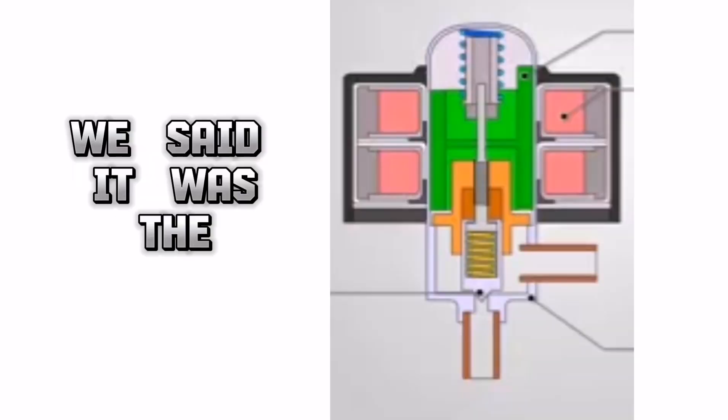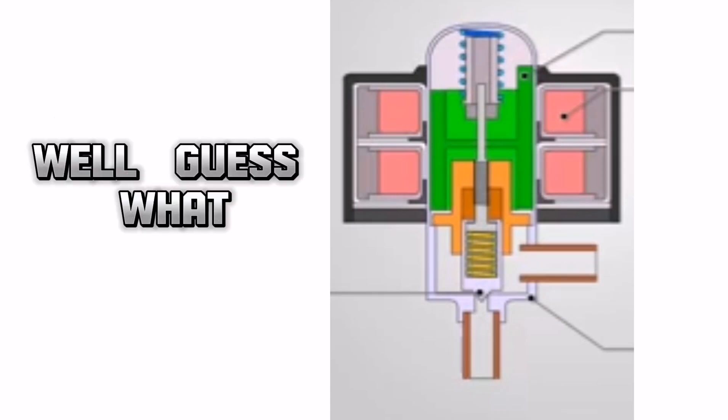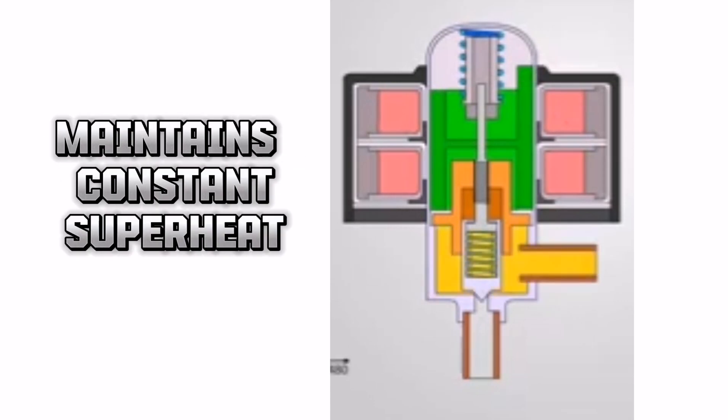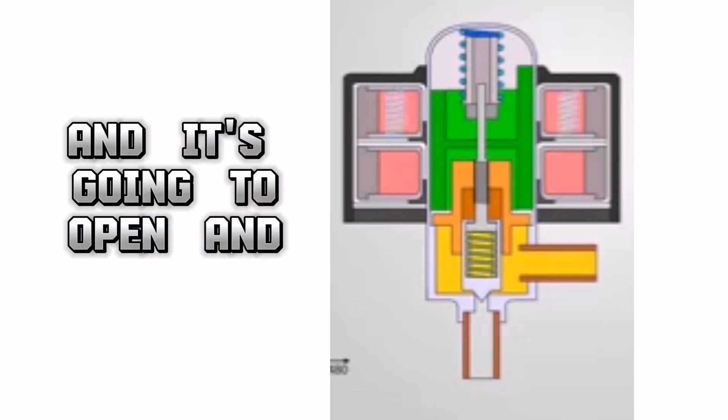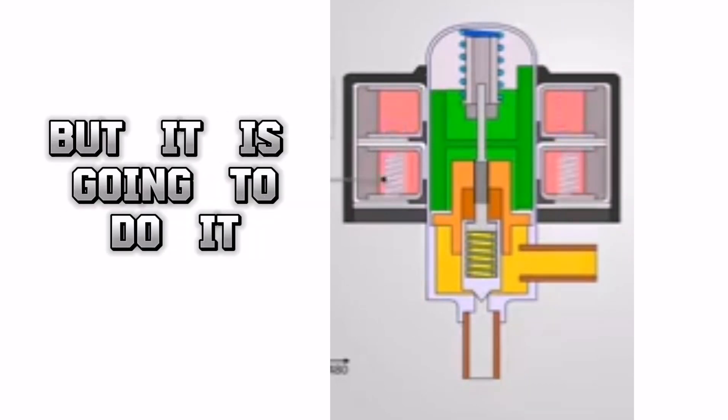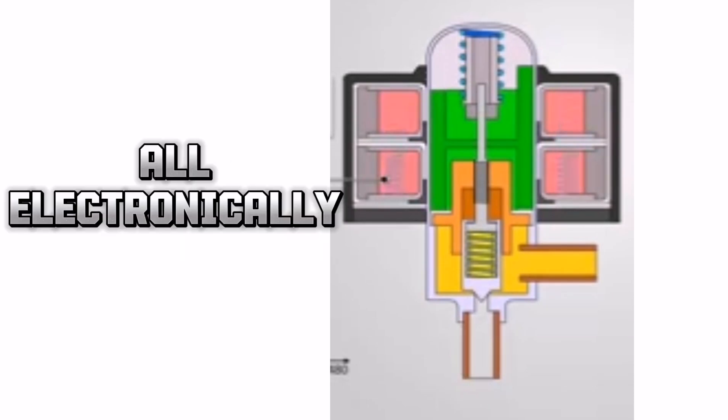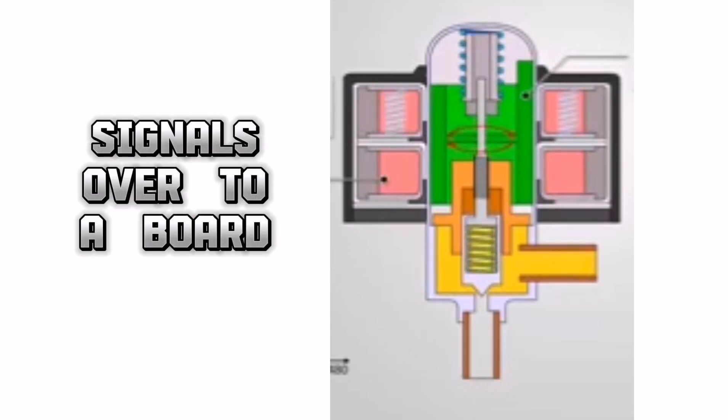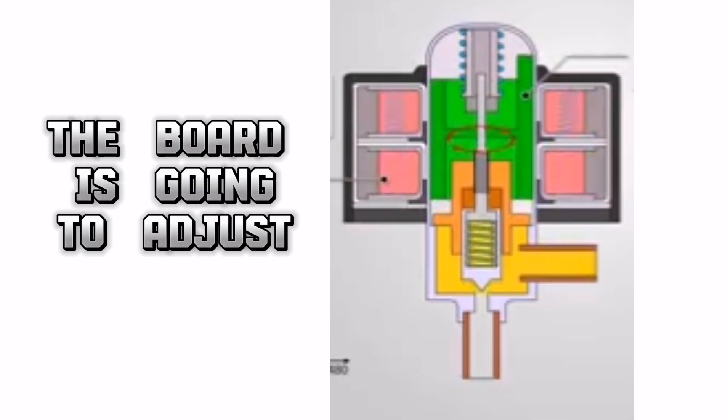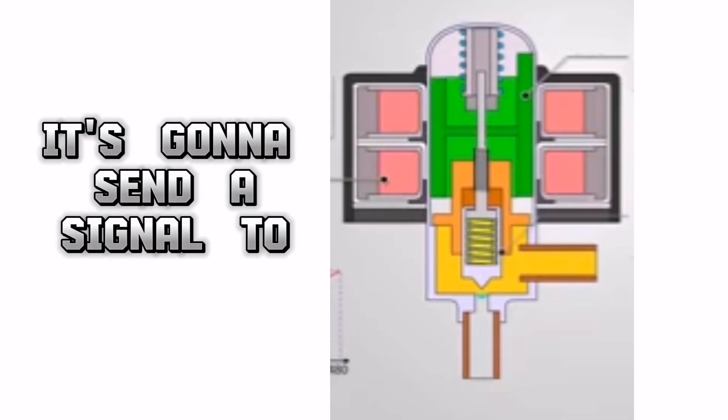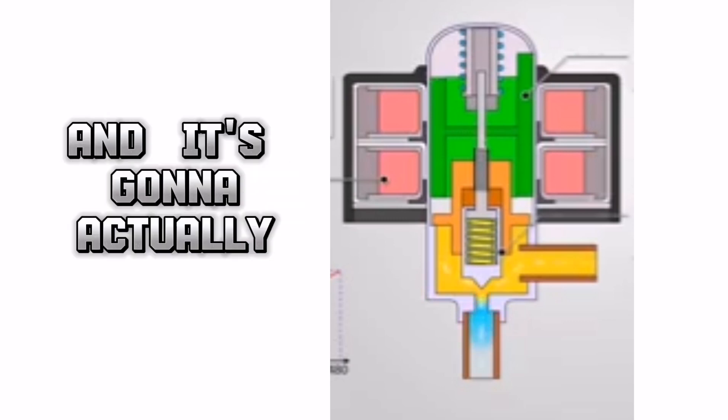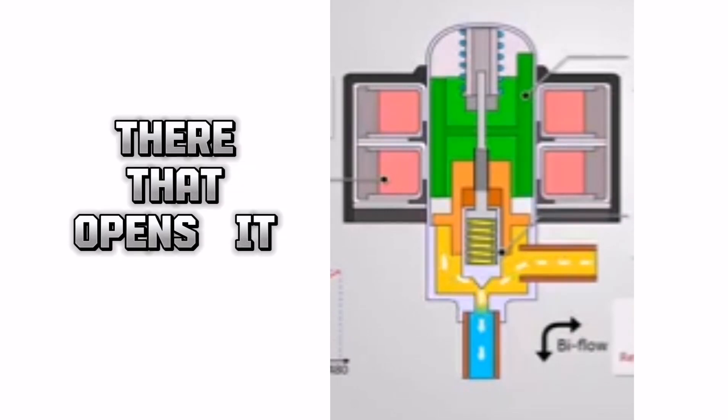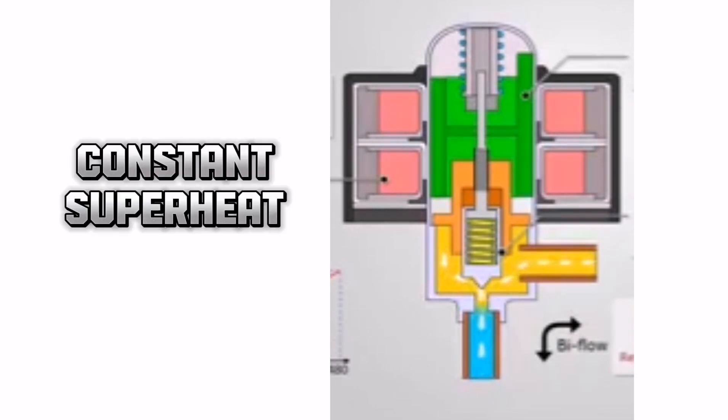Another one, we said it was the electronic expansion valve. Well, guess what? That's going to do basically the same thing. Maintains constant superheat. And it's going to open and close. And it's going to adjust. But it is going to do it all electronically. It's going to have to have sensors. Electrical sensors that are going to send the signals over to a board. The board is going to adjust. It's going to send a signal to the valve. And it's going to actually open and close the valve electronically. It's got a little motor in there that opens it. All of that to maintain constant superheat.